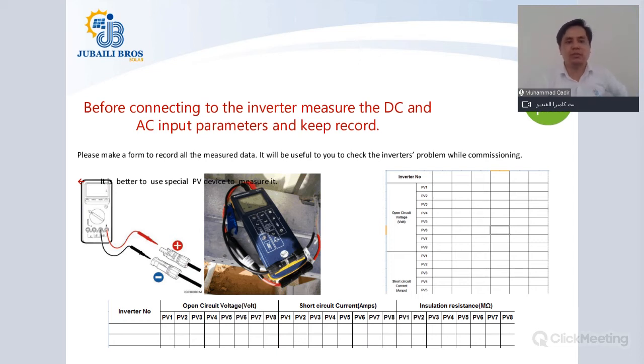Before connecting to the inverter, measure the DC and AC input parameters and keep a record. Sometimes people connect their solar strings directly to the inverter, and once they commission the inverter, they find that one of the strings is not working properly, which could be an installation issue as well. So they disconnect the solar string and try to find out what the issue is. If you make such tables before you connect your solar string to the inverter, it will help you understand how the inverter should operate based on the voltage, the short circuit current, and the resistance which you have measured.